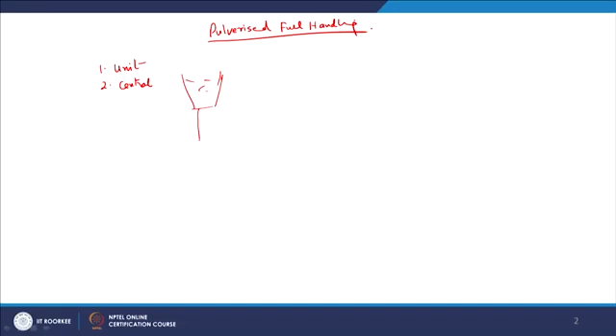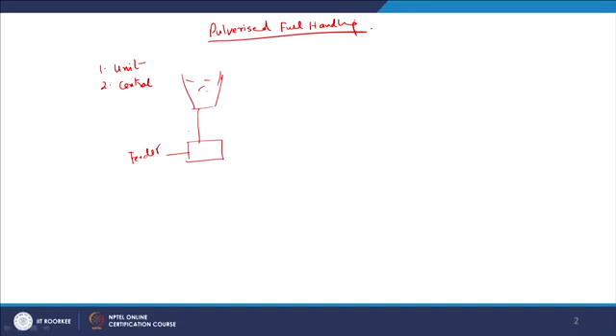there are big central systems, of course used for the big power plants. So, in the central system there are a number of pulverizers, and the pulverized coal is collected in the bin. From the bin it is distributed to different furnaces. So, we will start with the unit type of system. In the unit type of system, there is raw coal. The raw coal is sent to the feeder. This is the feeder.